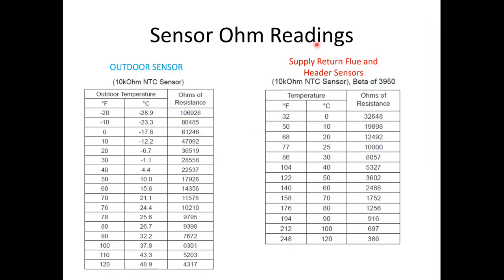In the manual, there will be the ohm readings for all of these sensors, what the outdoor sensor should be reading and what your supply, return, and flue sensor should be reading. Your supply sensor is also going to act as a high limit, as a manual reset high limit. There's 3 connectors, 3 wires on there. It'll be red with a gray line, and gray. They're looking for the same resistance between them. It is listed that it can be a form of manual reset high limit. Your first form of manual reset high limit, if the control sees temperatures over 210 degrees, it goes into a hard lockout.